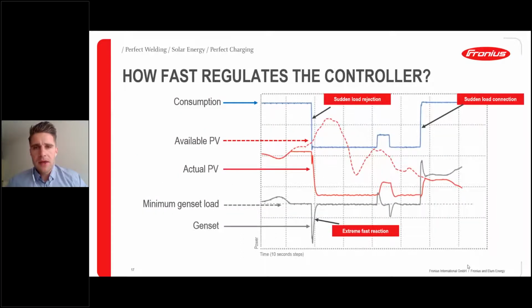That's the number 1 goal. I've put here one quick graph I want to show you, which demonstrates how fast this controller is regulating. Just look at it, bottom up. Therefore, you can see the minimum genset load. That's the genset, which is all the time at 30%. That means 30% of the load is all the time supplied by the genset. That's depending also on the genset manufacturer, but most of them tell that a minimum genset load of 30% of the load situation has to be met by the genset.